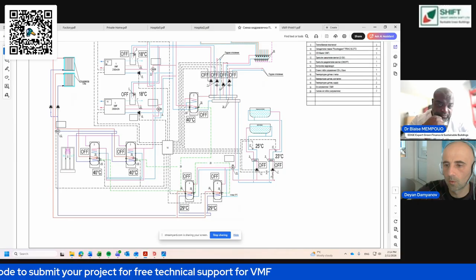Then in this project we have 3 VRF units covering heating, cooling, ventilation, humidity control, and also serving as backup for domestic hot water to the main sun water system. All 3 VRF units supply into one central buffer tank, and from this buffer tank, through the water distribution collectors, we go to different zones. We supply underfloor heating in different zones, the chill beams, heating and cooling ceiling panels, and water for the VRF supply coil itself.